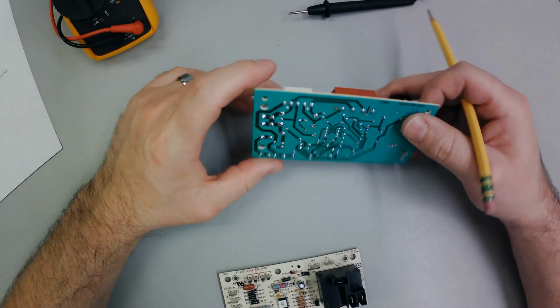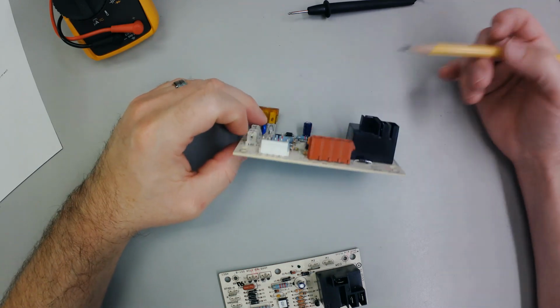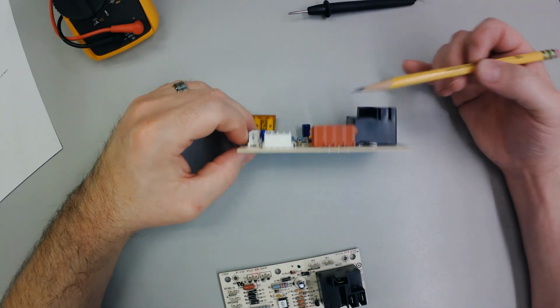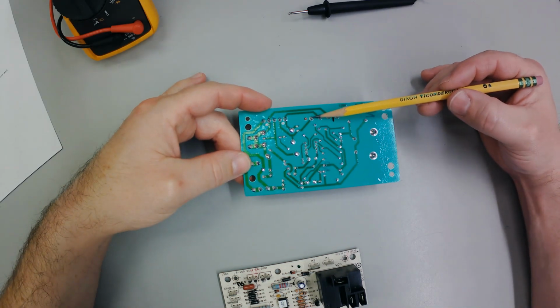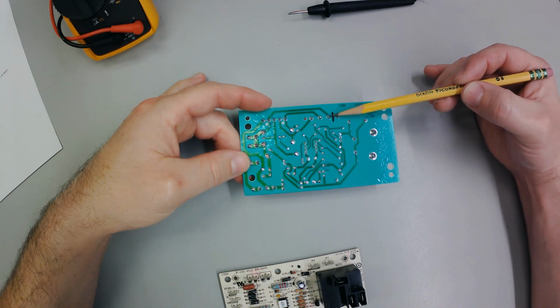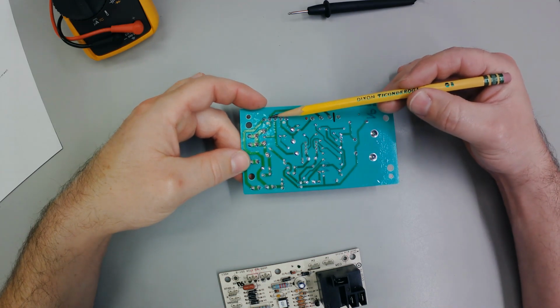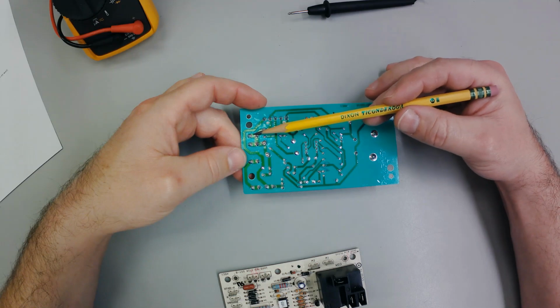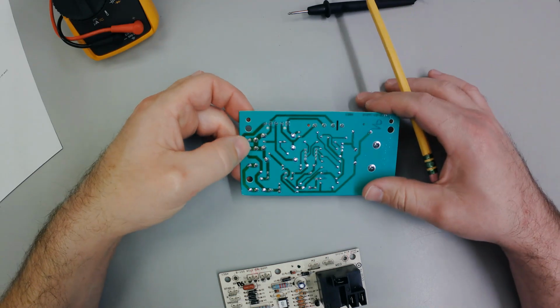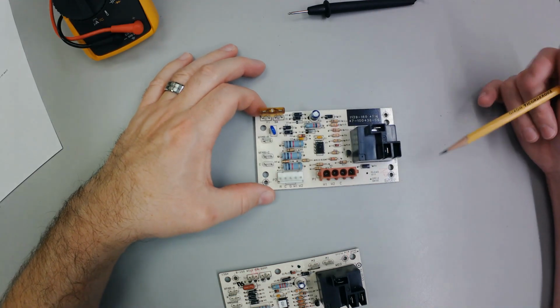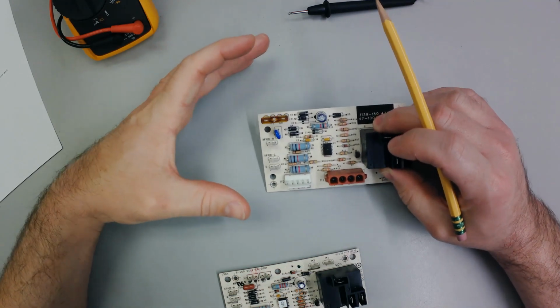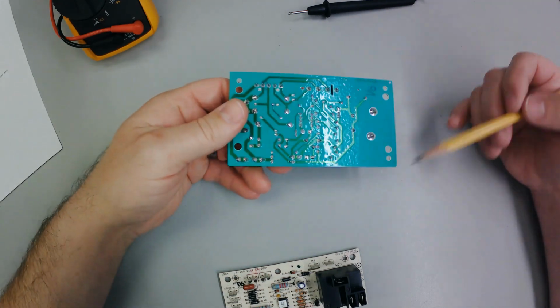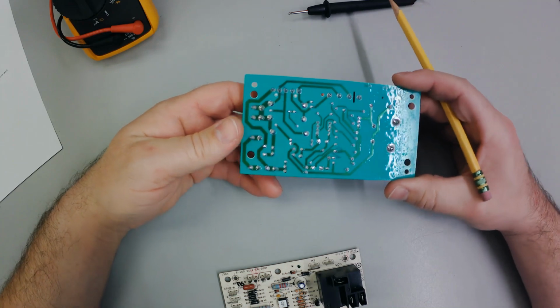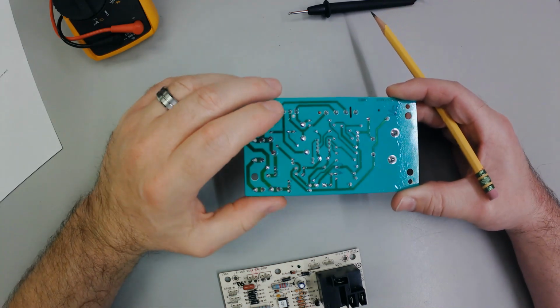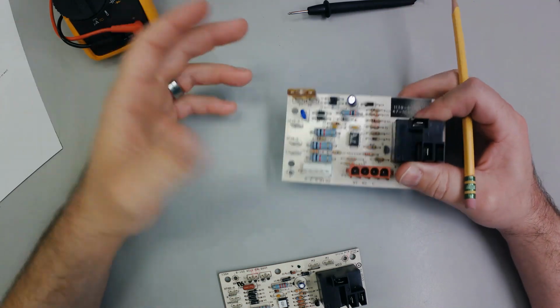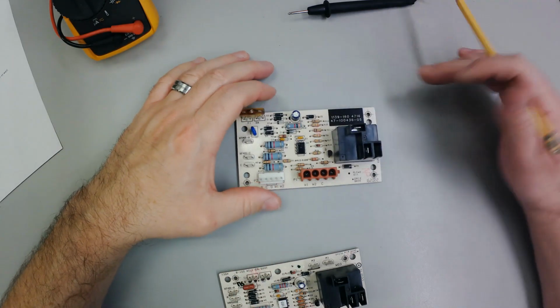It's all the same. So if we were to flip this over, common is the 3rd pin on this red plug, and I can see it here. 1, 2, 3. It's the 3rd pin. It loops over to this common, right, which backtracks to the transformer common and the regular common terminals. So don't be afraid to look at these boards and flip them over. A lot of times guys will flip them over and they'll find a burn spot where somebody puts 120 volts or 240 volts onto a low voltage circuit, and it just fries the back, fries the circuit board.